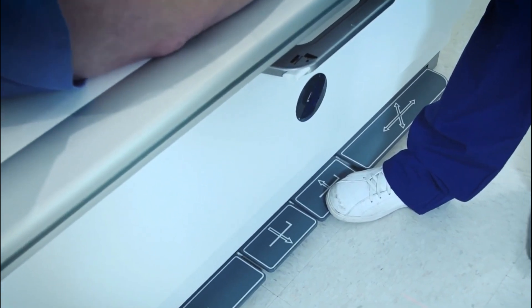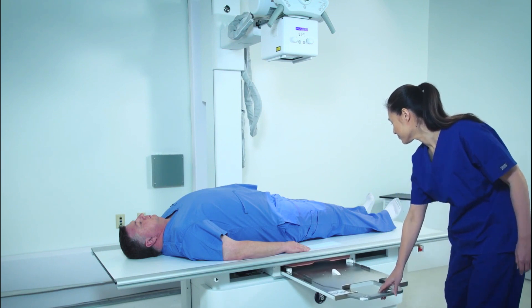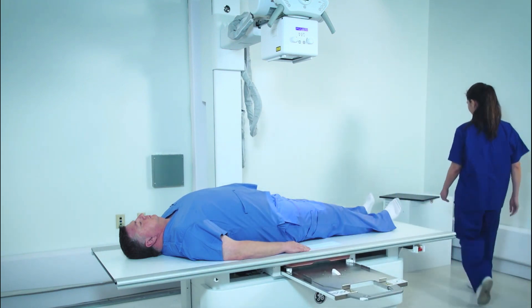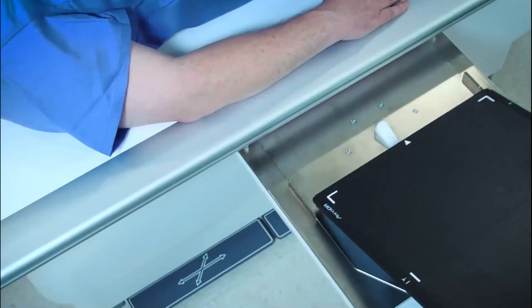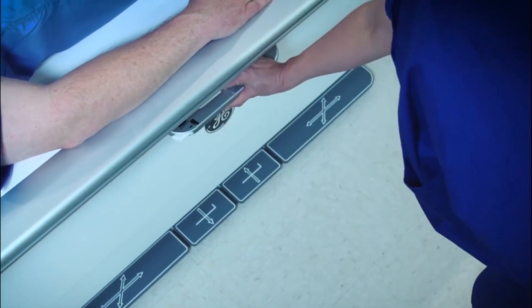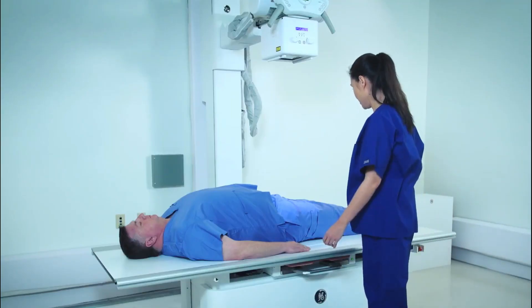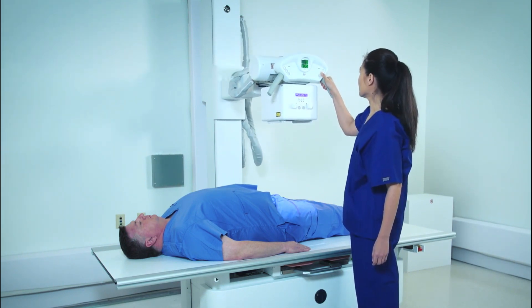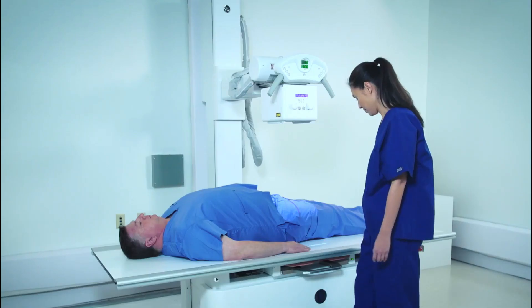Let's look at what a Bucky is in an x-ray machine. A Bucky is typically used for table or wall-mounted x-ray systems and holds the x-ray cassette and grid. It is a drawer-like device underneath the exam table that the cassette and grid are slid into before shooting the x-ray. A reciprocating Bucky moves the grid while the x-ray is being taken, keeping the lead strips from being seen on the image. The finer the lead strips, the less movement is needed.